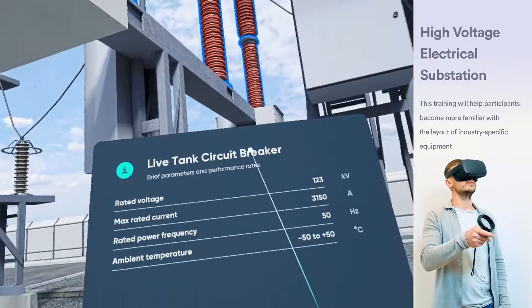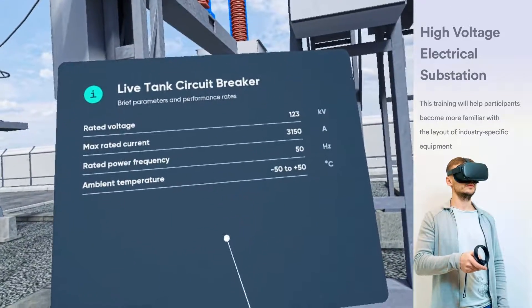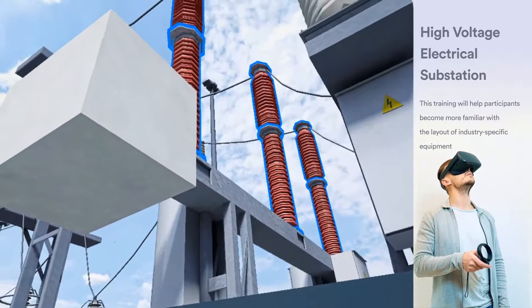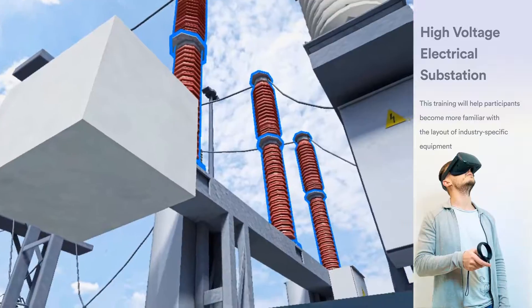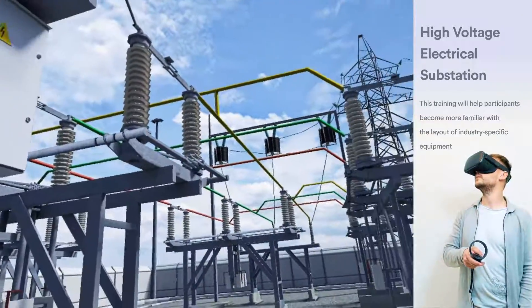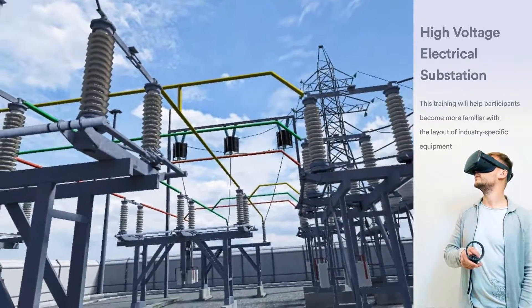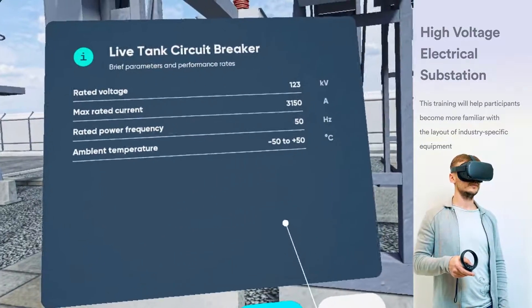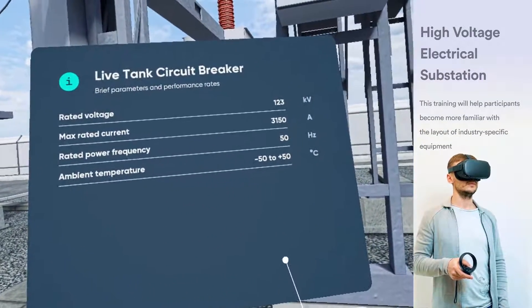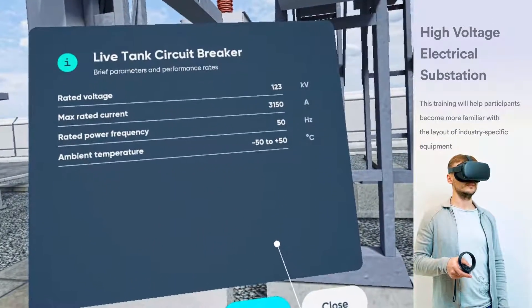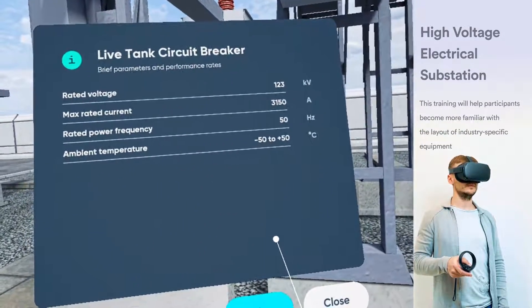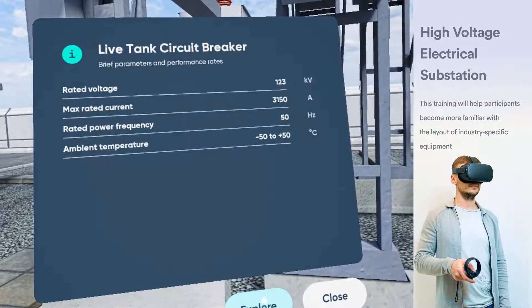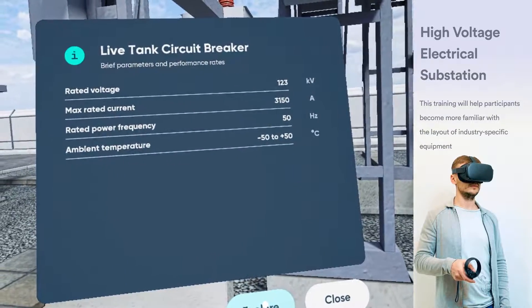The main task of a circuit breaker is to interrupt fault currents and to isolate faulted parts of the system. A circuit breaker must also be able to interrupt a wide variety of other currents at system voltage, such as capacitive currents, small inductive currents, and load currents. A brief specification is presented on the table.